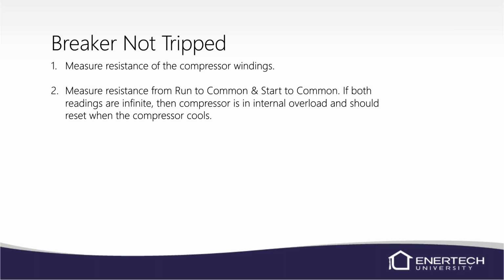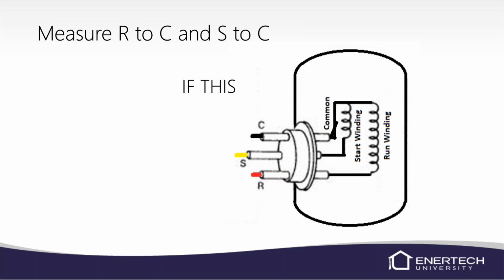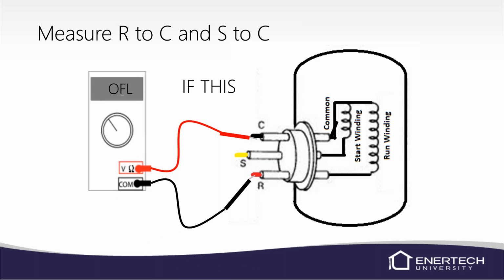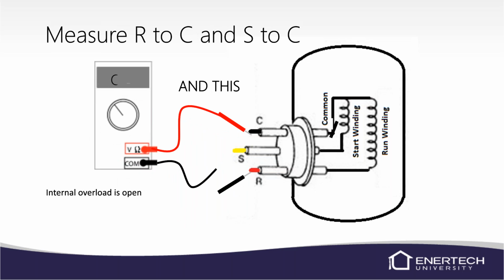Definitely run the unit and see what's going on with it. If it is hot, like I said, if it's in a space where you can get some water on it, go ahead and run some water over it, or put some ice bags on it. If not, you just have to wait for it to cool down. So measure run to common and start to common. If you get this and this, it's in internal overload. It'll say OL. Mine doesn't say OFL, mine says OL on the meter. If you get that reading, then it's in internal overload.